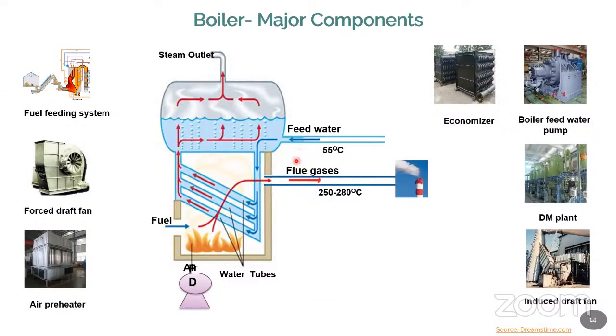We can take the heat from here by putting a separate pipe here. In that pipe, the feed water goes inside. Let us assume it's a spiral pipe in the duct, in the flue gas duct, like this. In the spiral piping system, if you flow the feed water, it will flow through this piping system and get the heat from the flue gas. Automatically, the temperature of the water will increase. Now that water will be given as input to the boiler. So you are reducing the flue gas temperature by passing the heat available in the flue gas to the water, which is used as feed water. So this is the economizer principle.